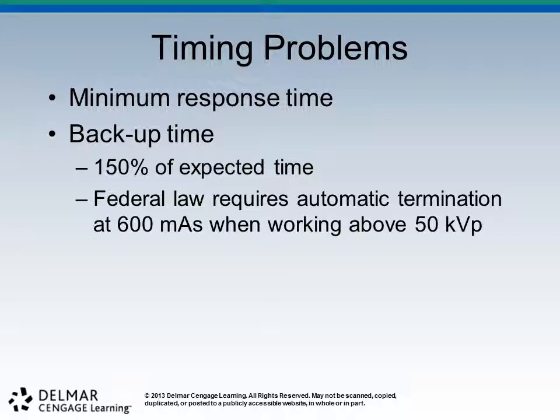The other thing, and I skipped over it, but it's something I want to talk about, is minimum response time. Phototimers have to stay on until they reach some sort of exposure, and most modern AECs, page 510, have a minimum response time around 0.001 seconds. That's probably faster than you can depress and release the button. If we get below that, we can cause some problems. If we do, that problem specifically is probably going to be something known as quantum mottle, which we touched on before.